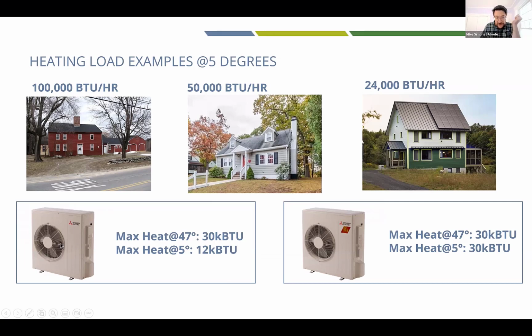So one is on the left-hand side, and this heat pump on the left-hand side, when it's 47 degrees outside, is 30,000 BTUs. But when this is at 5 degrees outside, this heat pump only has 12,000 BTUs. So say I took this heat pump and I put it in the leaky old farmhouse. I would need 9 of this outdoor piece of equipment to be able to fully heat the house when it's 5 degrees outside.